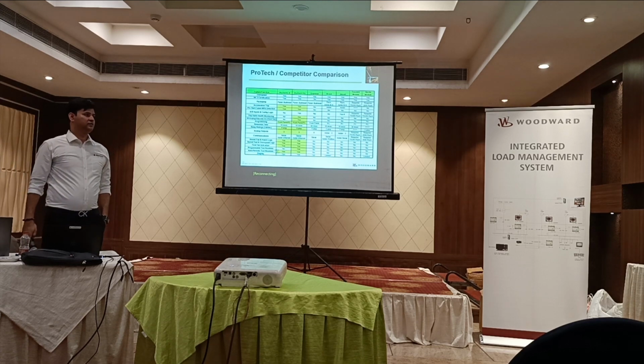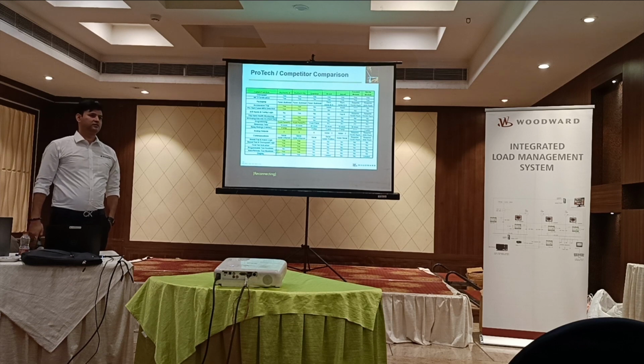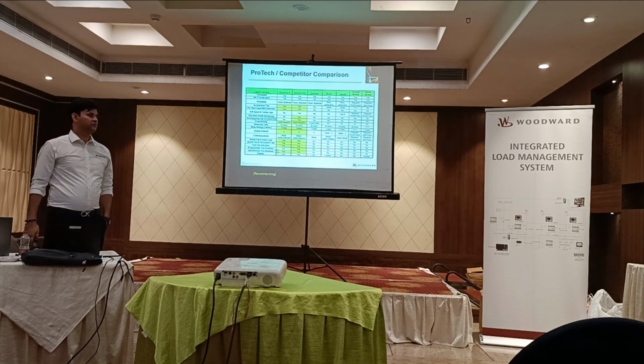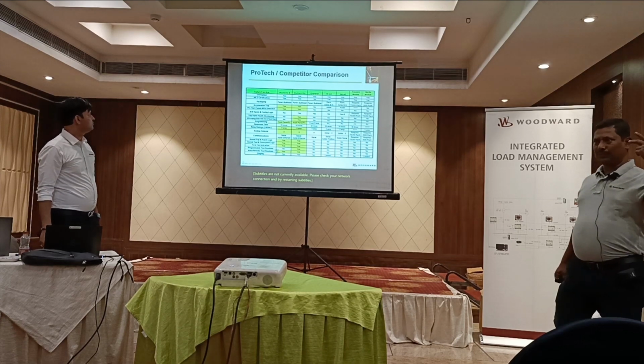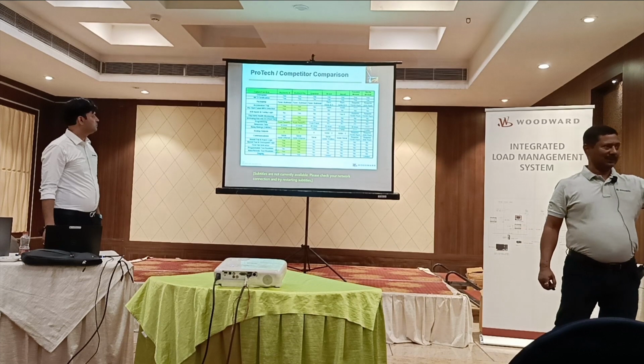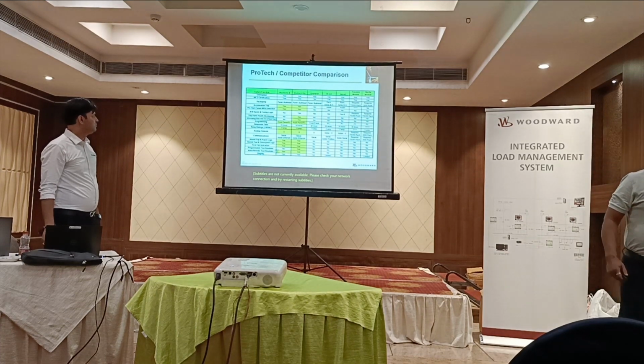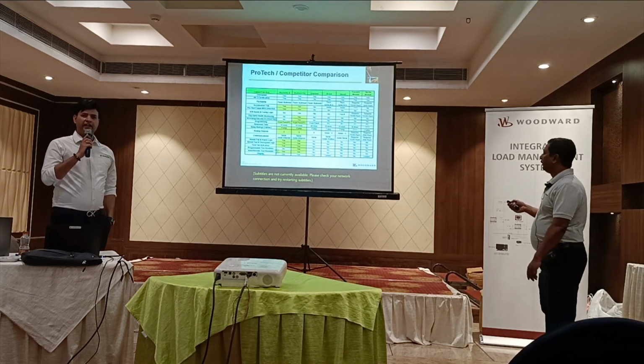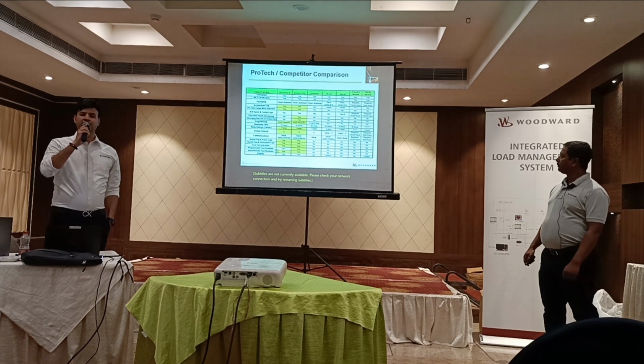We have a ProTech here, and inside the Protect there are 3 modules. And the 3 modules process the signals, the information, and then if 2 out of 3 modules say yes, we should trip, then it will trip.